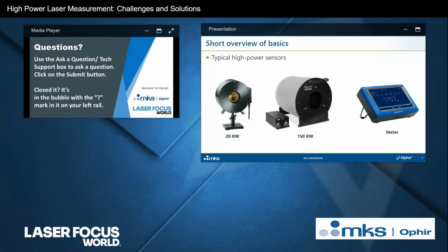Here in the middle, you see a sensor that measures up to 150 kilowatts. Just to give you a sense of scale, that one, it's 50 by 50 centimeters. It's not very big, sits on the desktop. And just for completeness, the sensor will normally work with a meter, sometimes referred to as a display. Every manufacturer has their own terminology, and the meter is how the user would interact with the measuring instrument, controlling the various parameters, wavelength settings, scales, and so on, and of course, seeing the output.